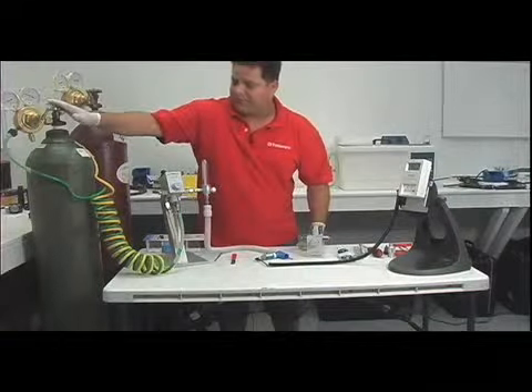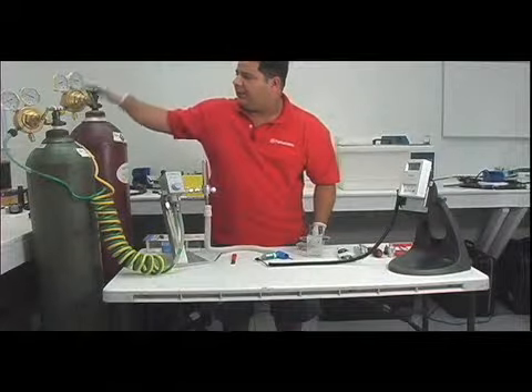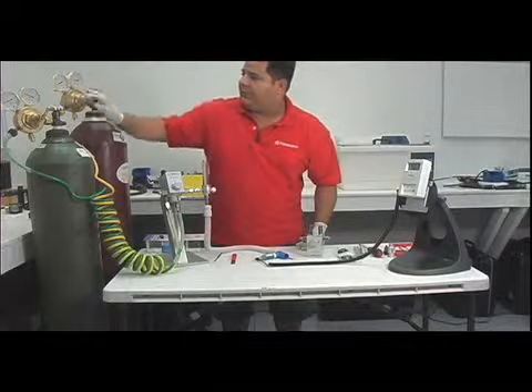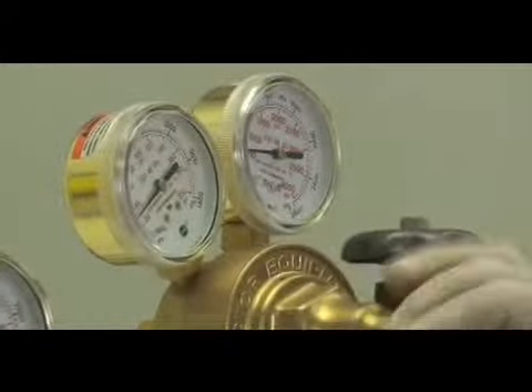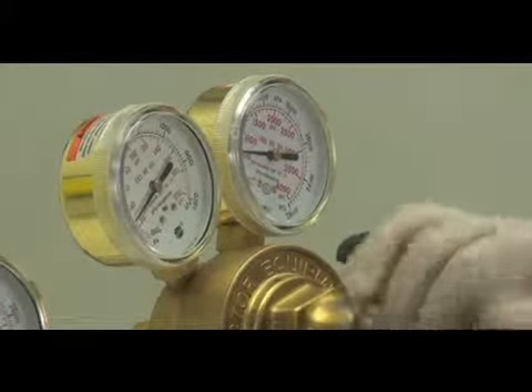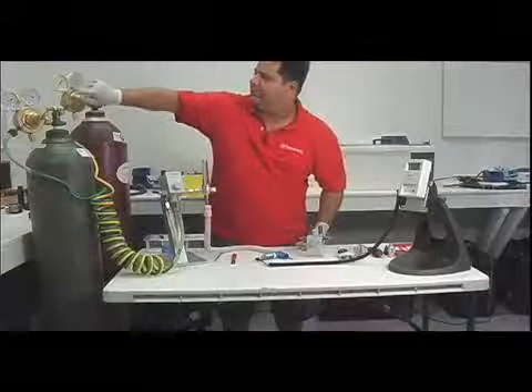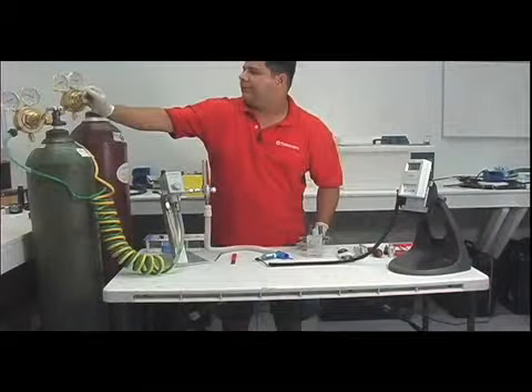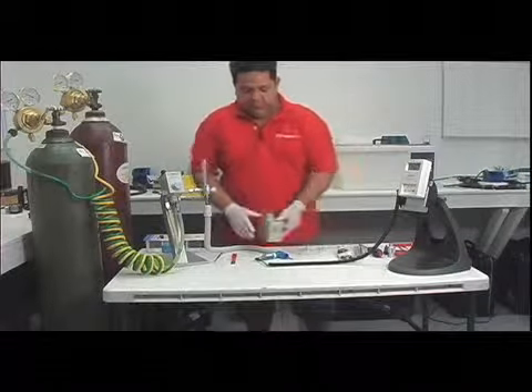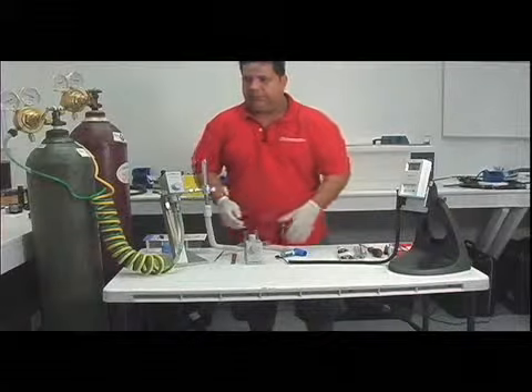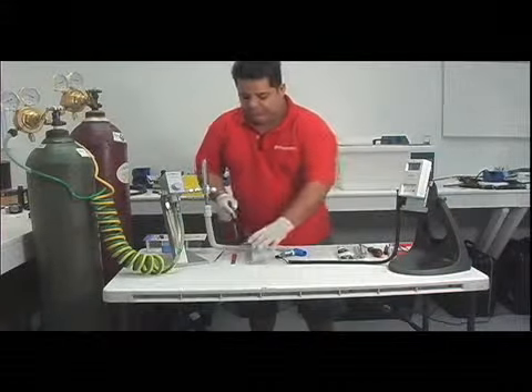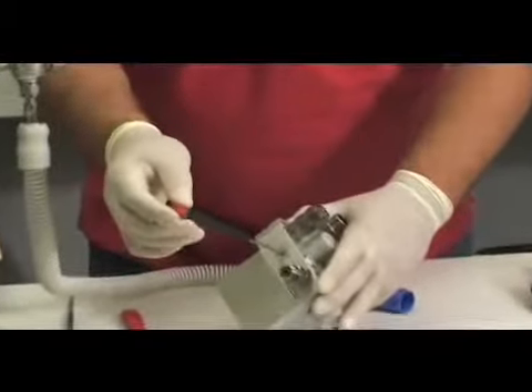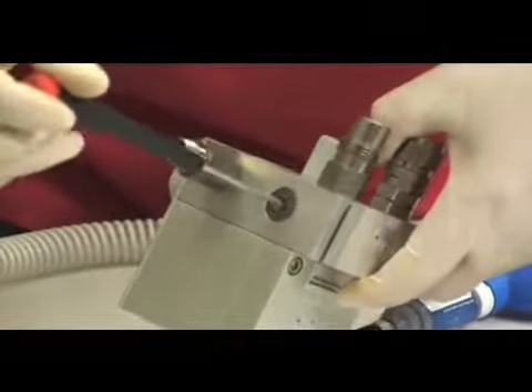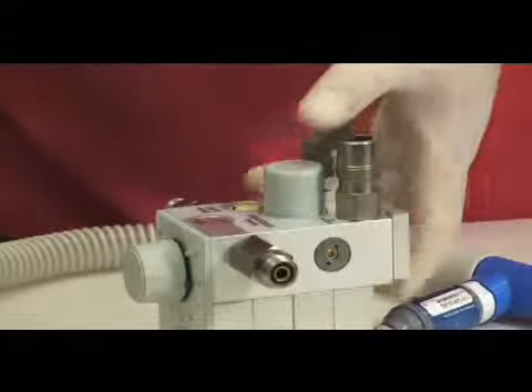That's on the oxygen side, and we need to repeat that also on the air side. So we'll lower our pressure down to 30 or lower, and the alarm goes off. So we reestablish the pressure up to 50. So whenever you have either not enough or too much, by controlling these screws in and out, you pretty much get the right calibration on the alarm once it's hooked up.